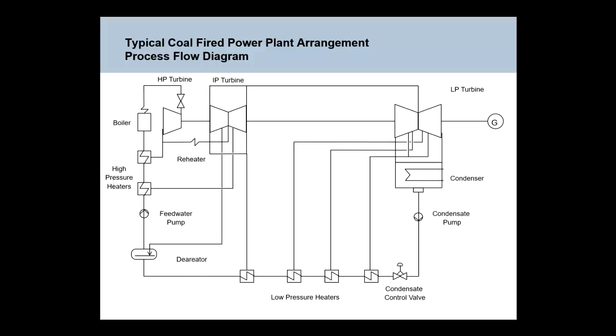The efficiency of this picture depends on having the highest pressure and temperature at the inlet to the turbine and the lowest pressure and temperature at the outlet. Okay? On a modern utility scale unit, the pressure at the inlet might be above 20 megapascals, so it's 200 atmospheres, and temperature will be well above 540 degrees C, in some units approaching 700. Okay, so this is very, very high pressure, high temperature steam.